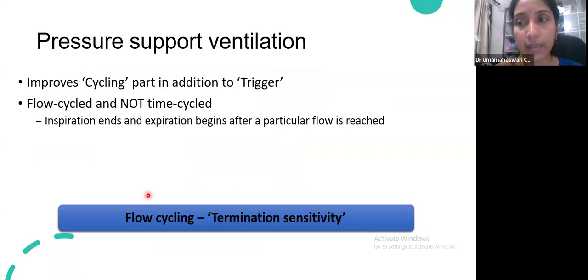So PSV is nothing but a flow cycled assist control. It also supports all the breaths taken by the baby. For example, you have set a rate of 40, and the baby is breathing at a rate of 60. All the 60 breaths will be supported by PSV mode. But the cycling, which is changing from inspiration to expiration, is not time cycled, it is flow cycled. What the machine does is, when the inspiratory flow is getting reduced, it recognizes that and switches over from inspiration to expiration.